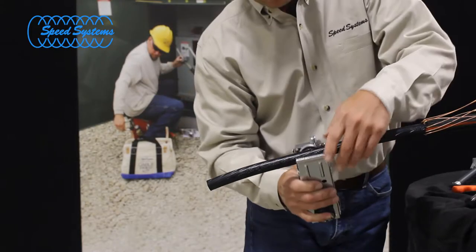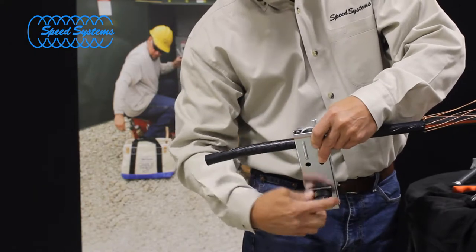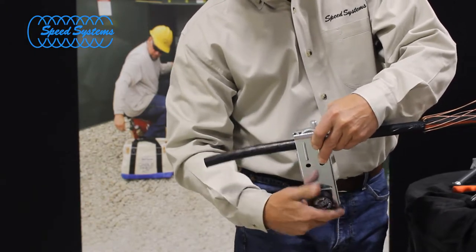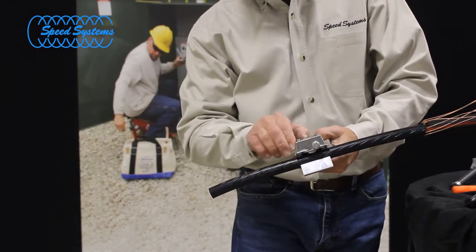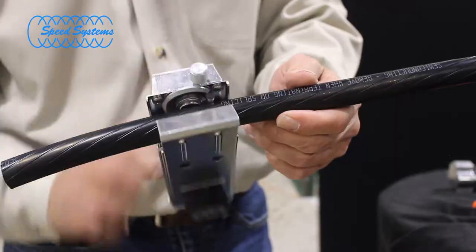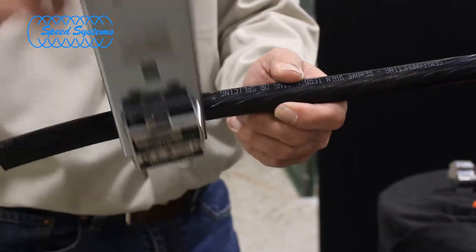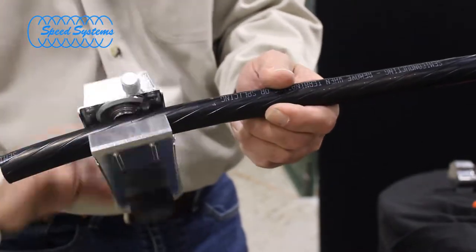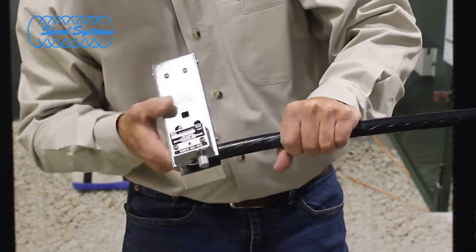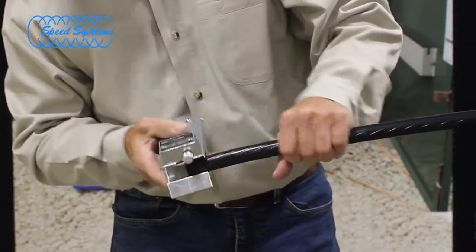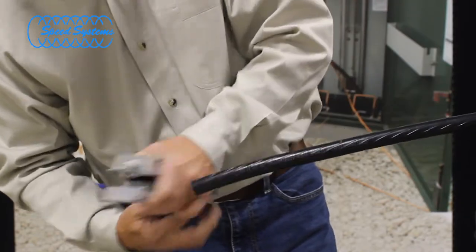Place the 1700SS on the cable at the point you marked. Make sure the cable is as straight as possible. Rotate the tool counterclockwise around the cable to make the square cut. Without removing the tool from the cable, move the blade lever to the spiral position and rotate the tool until it reaches the end of the semi-con. Open the jaws and remove the 1700SS from the cable.